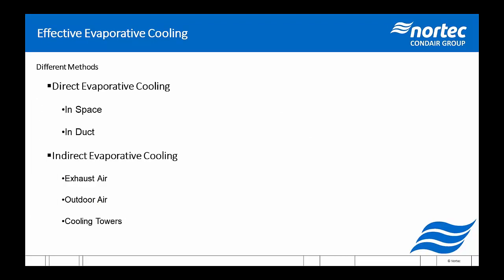So, different methods. There's direct evaporative cooling, which is humidifying and cooling the air that is going into the building or is already in the building. So that would be in space or in duct. And then there is indirect evaporative cooling, where we apply the cooling to either exhaust air or outdoor air, or even cooling towers, which is approximately the same as applying to outdoor air, but I'll show you the difference in a moment here.